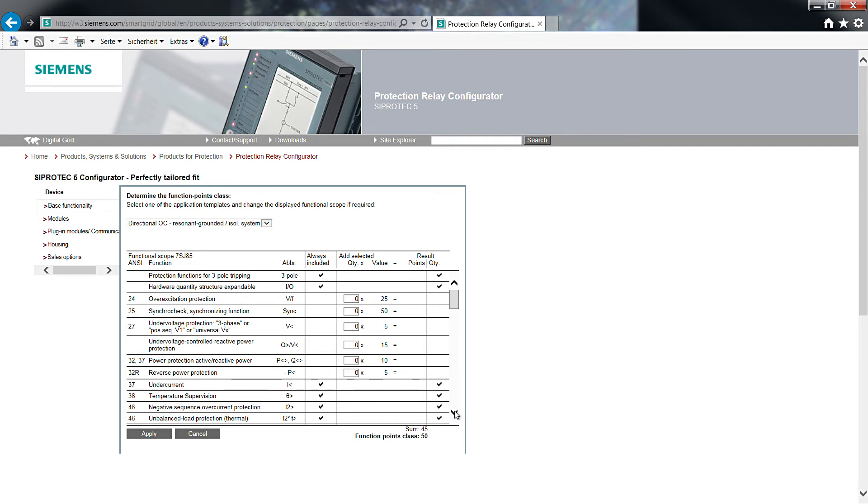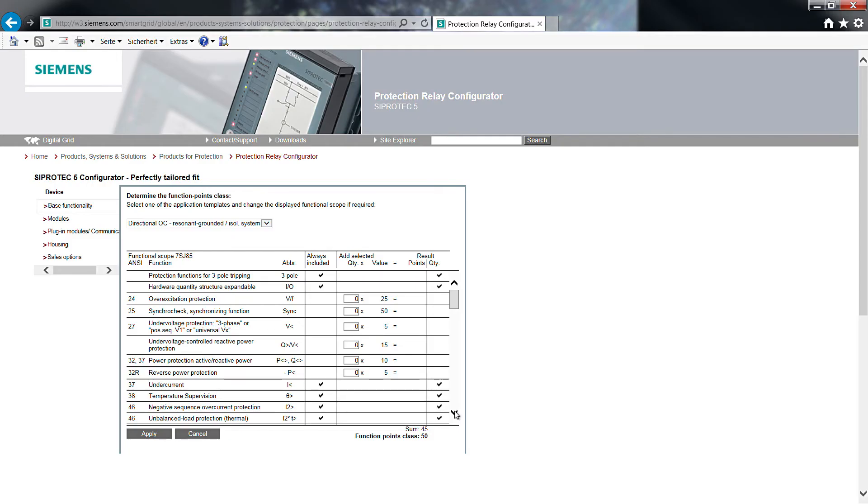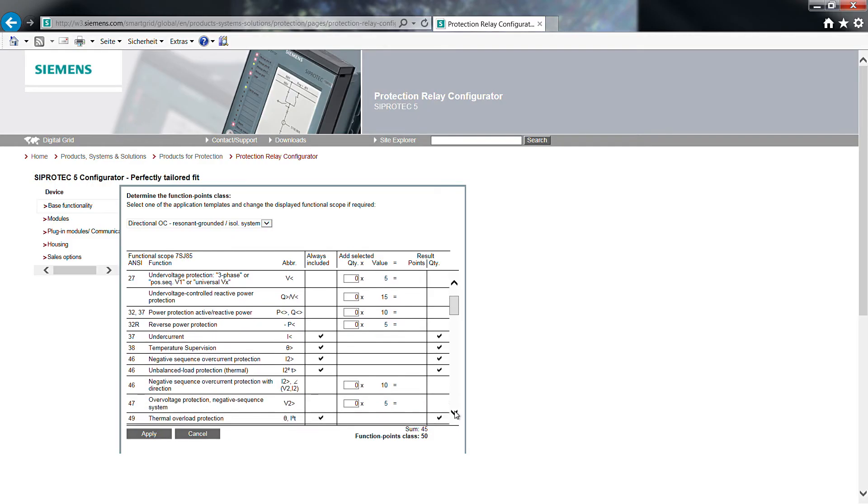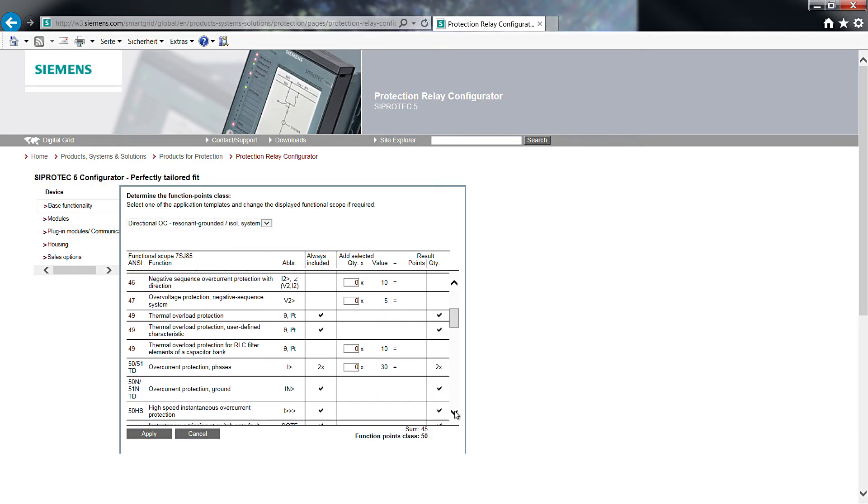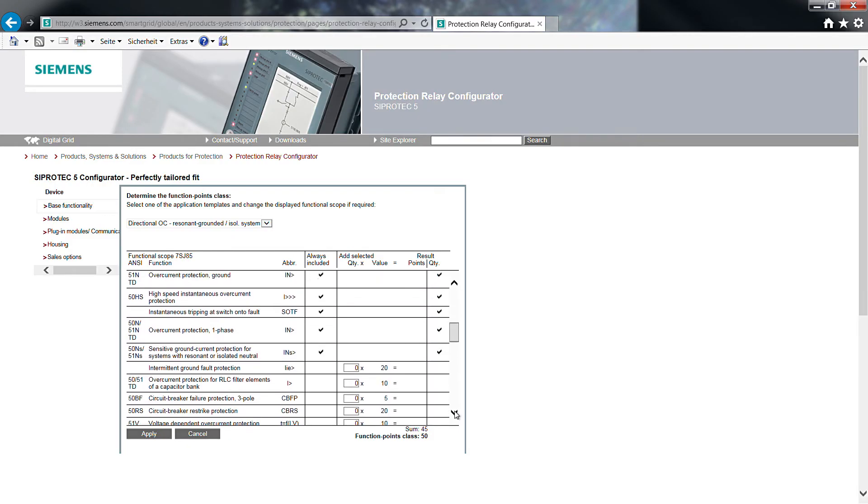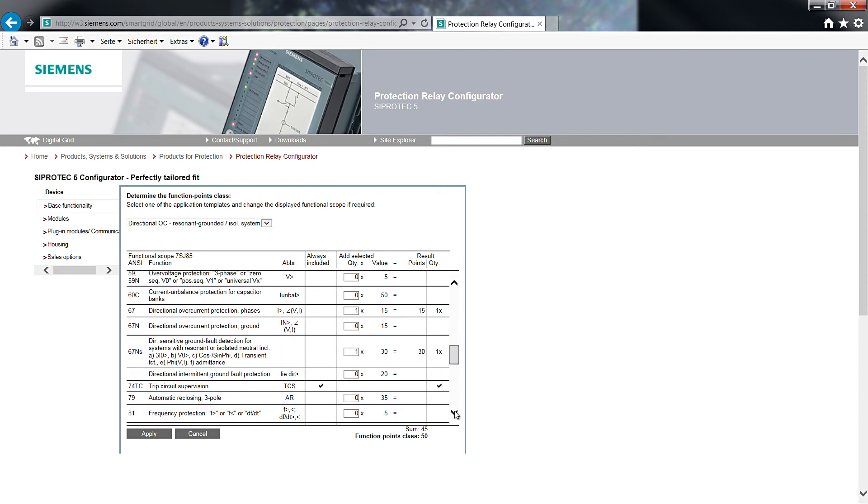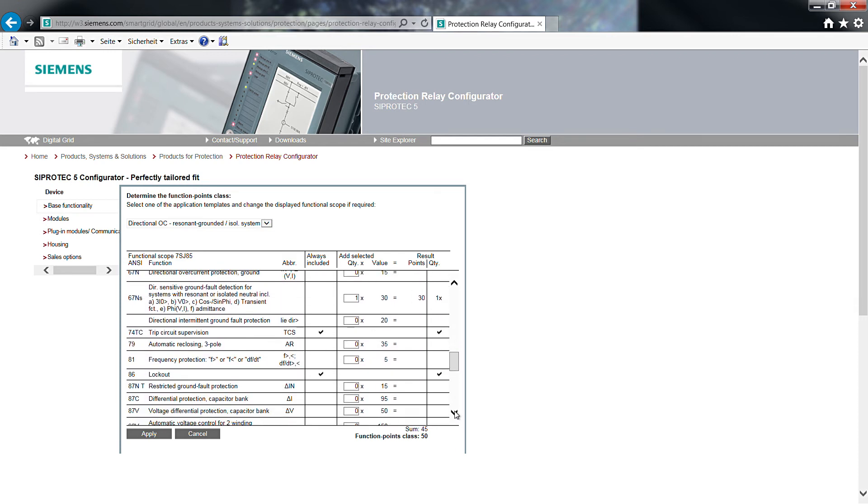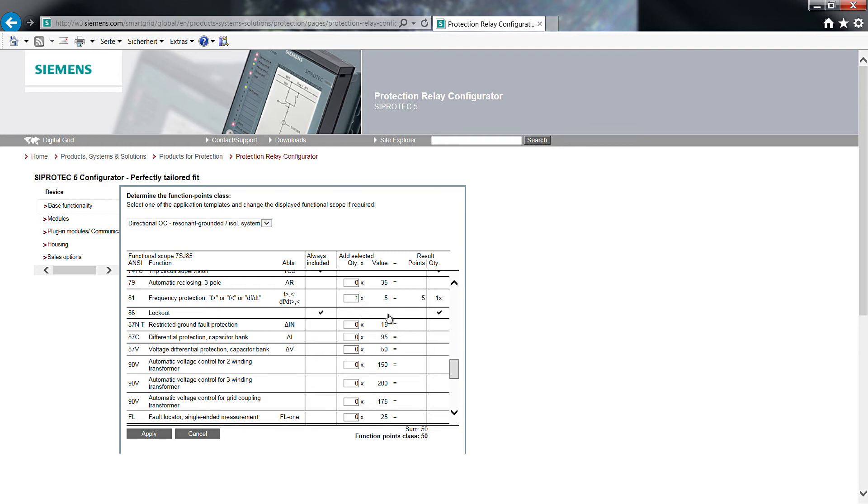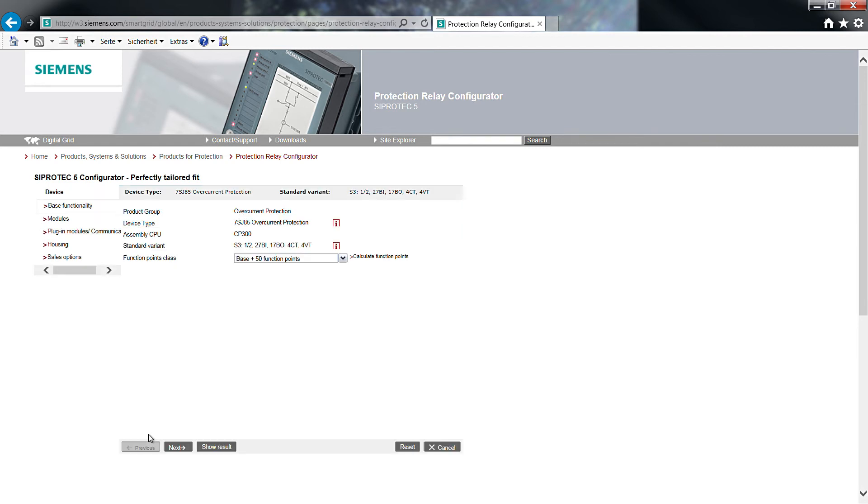But remember, according to the specification, the device should contain frequency protection. Therefore, we will now move the cursor downwards to the ANSI number 81 and select the frequency protection function once. The total of function points is now 50, which exactly fills up the function point class. With a click on apply, we can close this table.